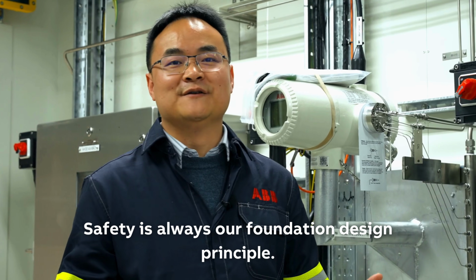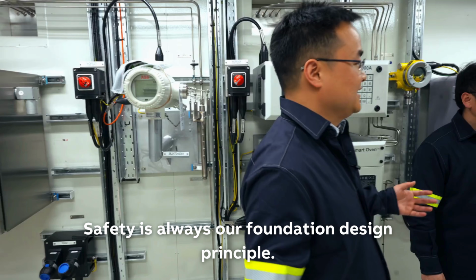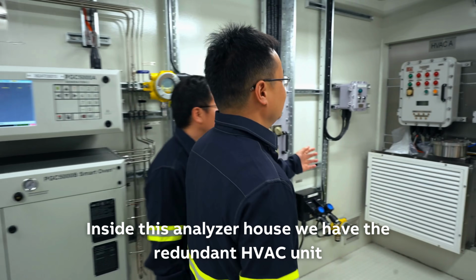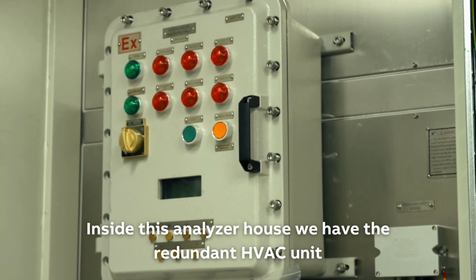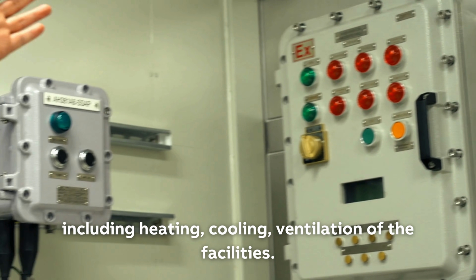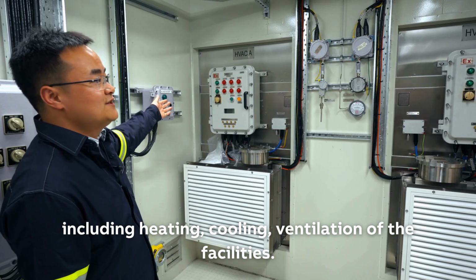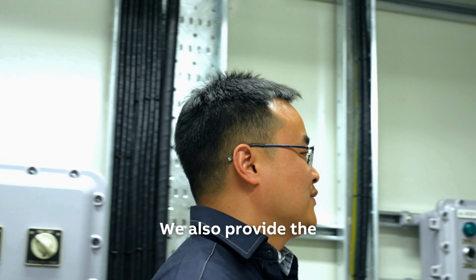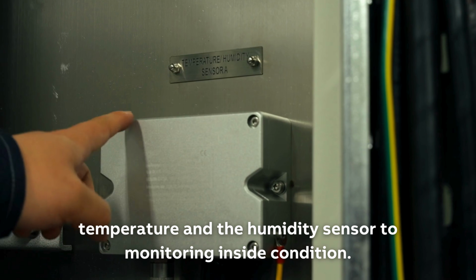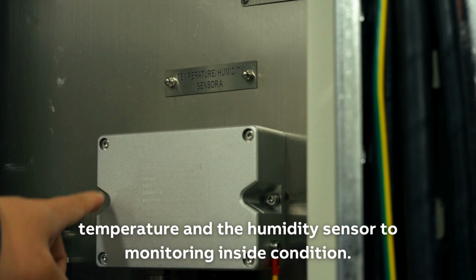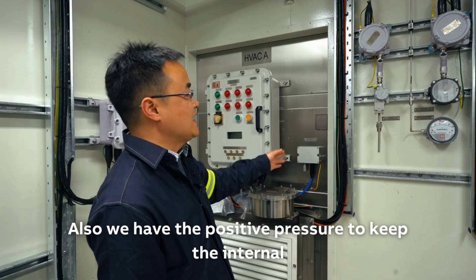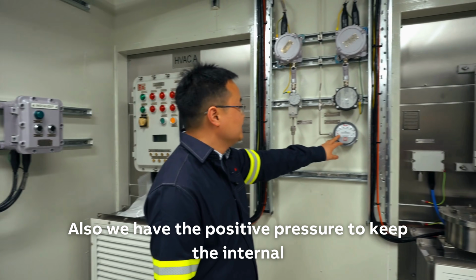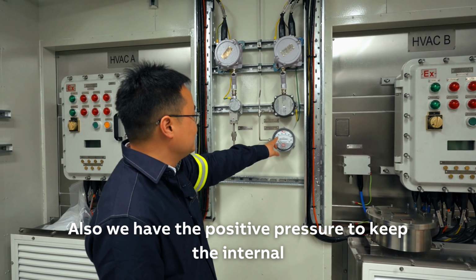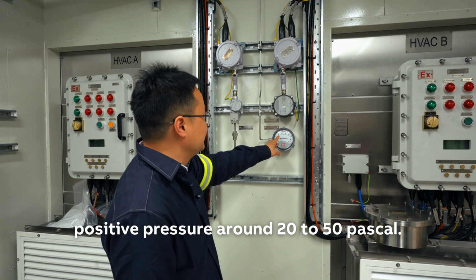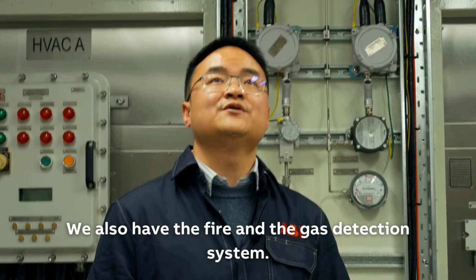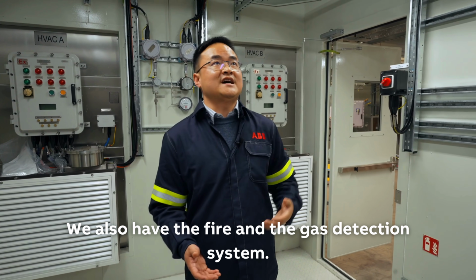Safety is always our foundation design principle. Inside this analyzer house, we have the redundant HVAC unit, including heating, cooling, and ventilation facilities. We also provide temperature and humidity sensors to monitor the inside condition. Also, we have positive pressure to keep the internal positive pressure around 20 to 50 Pascal. We also have the fire and gas detection system.